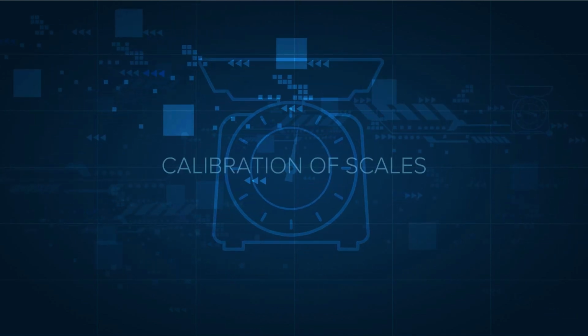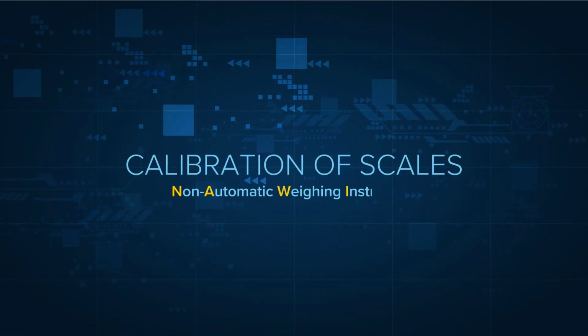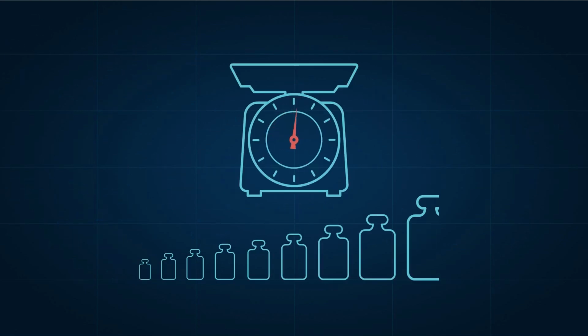Today, we're going to introduce you to the essential steps for the successful calibration of a non-automatic weighing instrument, better known as a scale. Each scale has a resolution corresponding to the smallest perceptible change of its indication, and a maximum capacity that corresponds to the highest value it can measure.